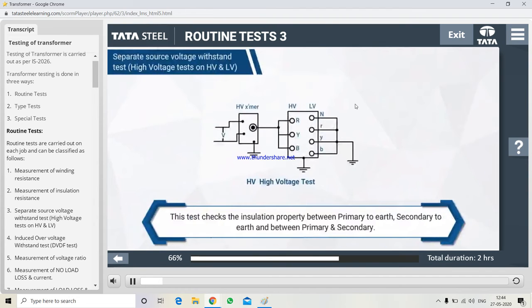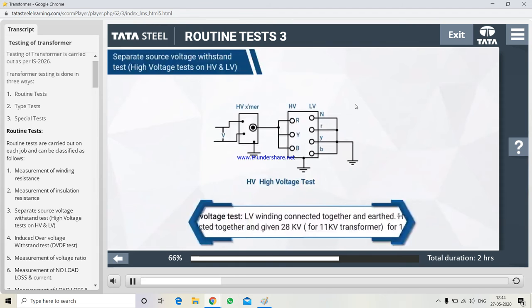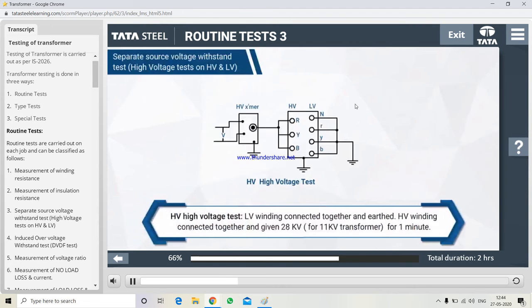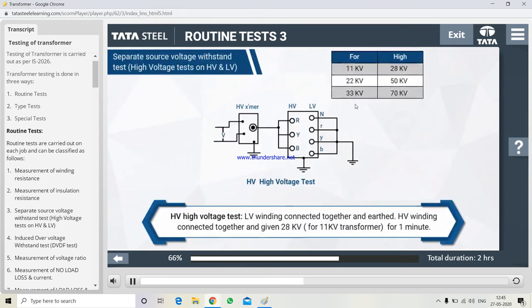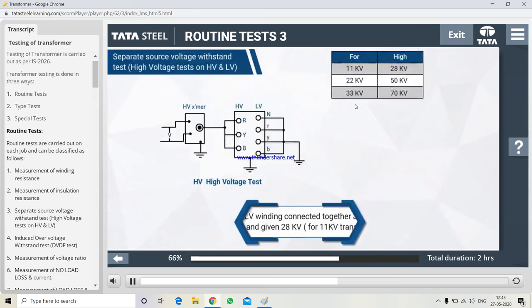This test checks the insulation property between primary to earth, secondary to earth, and between primary and secondary. HV high voltage test: LV winding connected together and earth. HV winding connected together and given 28 kV for 11 kV transformer for 1 minute.